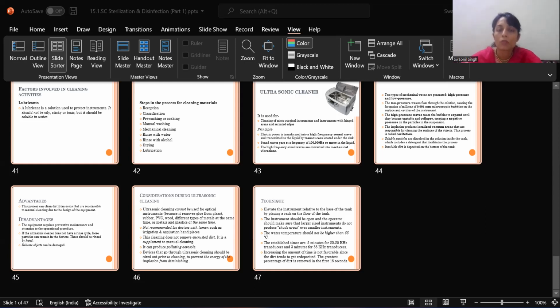Now, cleaning. What is cleaning? It is the removal of visible soil or particles, organic or inorganic, from the objects and surfaces, so that after cleaning, the sterilizing or disinfecting agent can come in direct contact with the items or surfaces which require thorough sterilization or decontamination. It is essential before high-level disinfection and sterilization so that the surfaces of the instrument cannot interfere with the effectiveness of these processes.